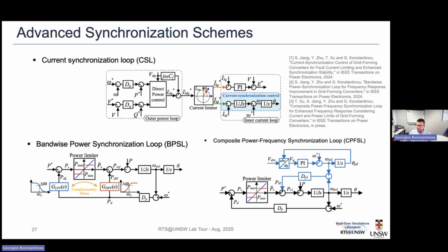A third way of thinking about it would be adding frequency aspects into this power synchronization loop. Our initial idea was the inclusion of a PLL. The PLL no longer synchronizes the converter to the grid - we still have a self-synchronized converter - but this additional information from the frequency loop adds damping power that we can add to the system, improving synchronization stability under current limited conditions and fault current limits.